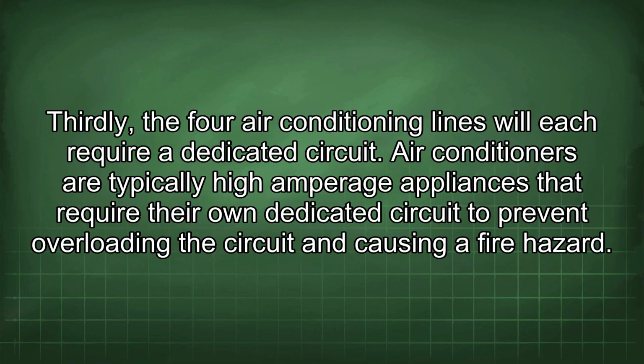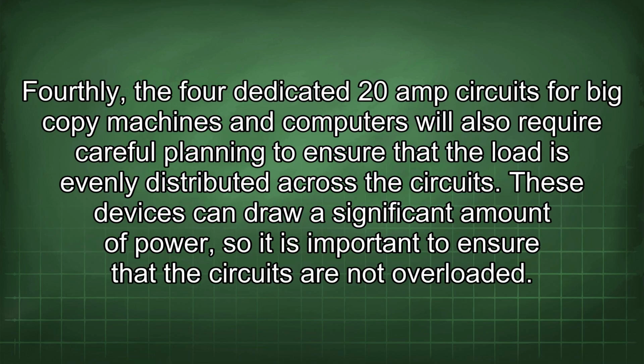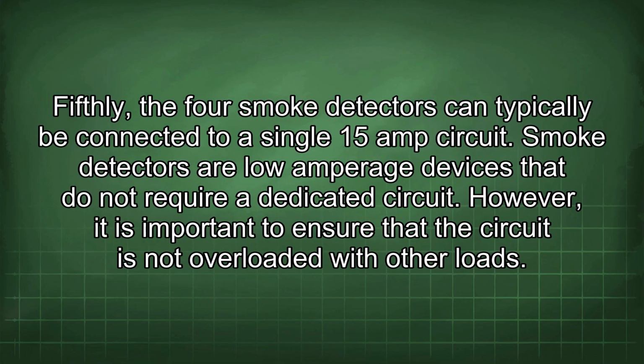Thirdly, the 4 air conditioning lines will each require a dedicated circuit. Air conditioners are typically high amperage appliances that require their own dedicated circuit to prevent overloading the circuit and causing a fire hazard. Fourthly, the 4 dedicated 20 amp circuits for big copy machines and computers will also require careful planning to ensure that the load is evenly distributed across the circuits. These devices can draw a significant amount of power, so it is important to ensure that the circuits are not overloaded. Fifthly, the 4 smoke detectors can typically be connected to a single 15 amp circuit. Smoke detectors are low amperage devices that do not require a dedicated circuit. However, it is important to ensure that the circuit is not overloaded with other loads.